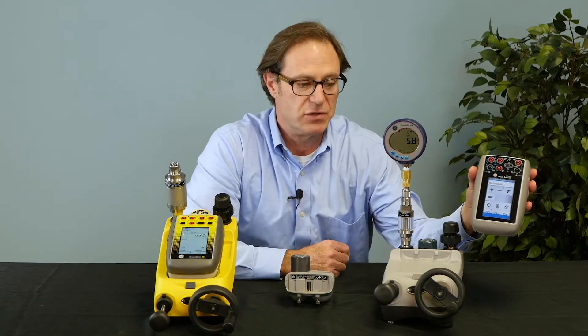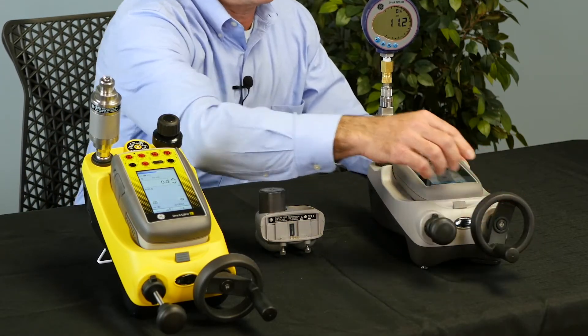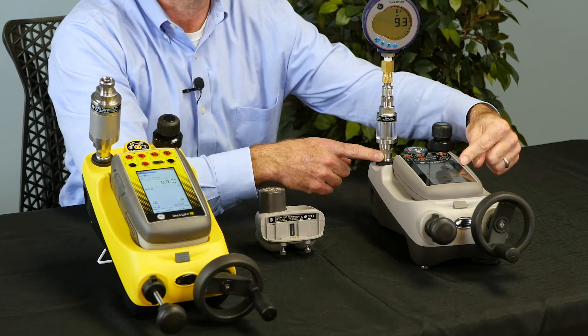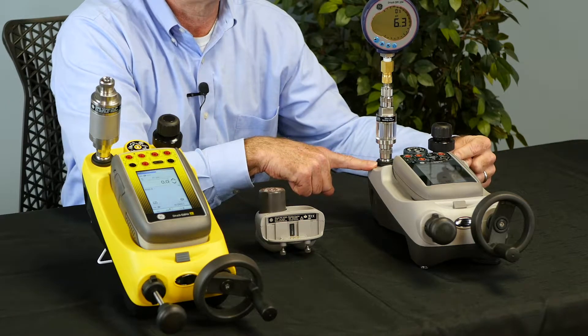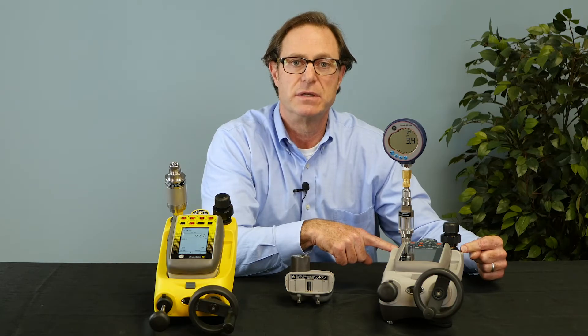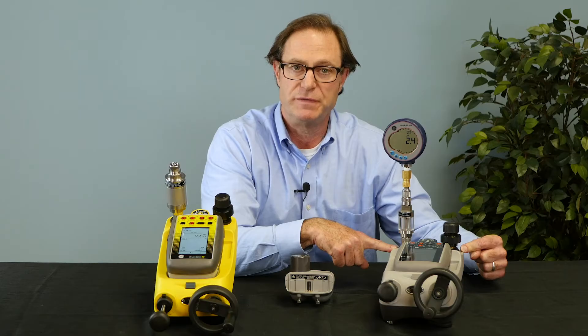The Druck DPI-620 unit clicks into these pressure bases which have an integral built-in hand pump, volume adjuster, test port, and vent valve. This is your reference pressure sensor which provides you a direct measurement of applied pressure on the DPI-620 itself. The pressure bases come in three versions: one pneumatic capable of up to 300 psi, a second pneumatic base capable of up to 1,500 psi, and a third hydraulic base capable of up to 15,000 psi.